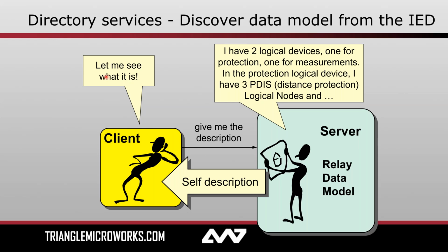Ultimately, as a client, you really only have two ways to learn about the device that you're communicating with. Either you provide an SCL file, which defines the data model of the server. This could be an SCD file that defines the data models, parameters and configurations of all of the IEDs in your substation, or it might be a CID or an IID that defines just a particular one, or even an ICD, depending on what stage you're at in the engineering process. However, there is another mechanism. Instead of providing that SCL file to the client, you can just ask, as the client, hey, server, please give me a description of yourself. And this uses the underlying directory services to issue that request and then receive the description back.